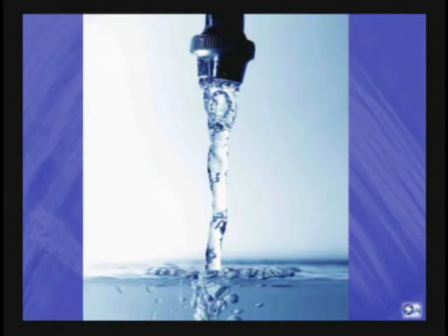So let's go off on the side here and talk about asbestos in water. Asbestos can be found in your water by two main pathways, either by runoff through naturally occurring asbestos or by travel through asbestos-containing aqueducts like our cement asbestos pipe. There are an estimated 200,000 miles of asbestos cement pipe in the US.